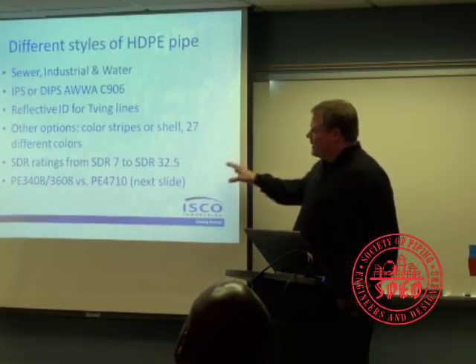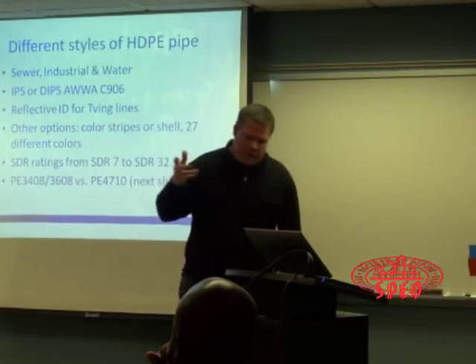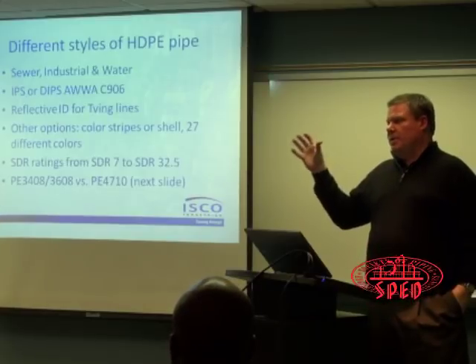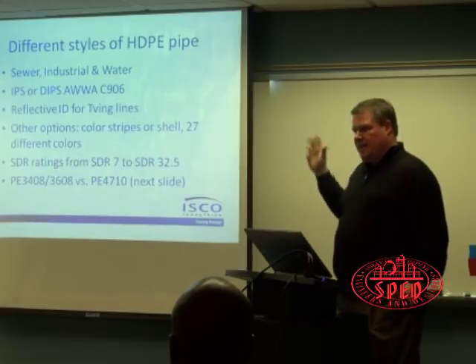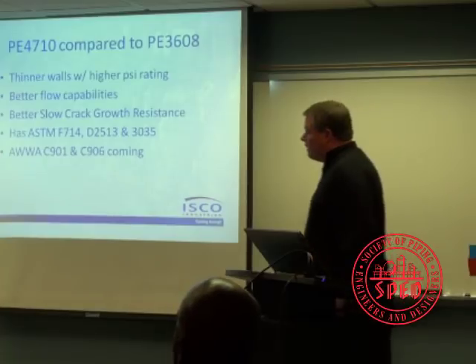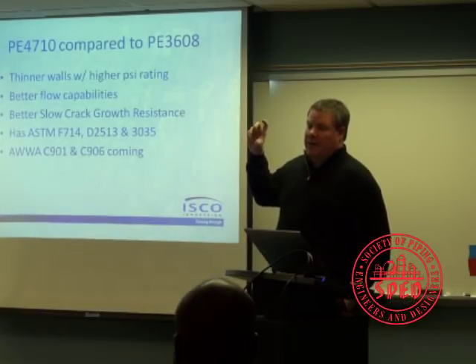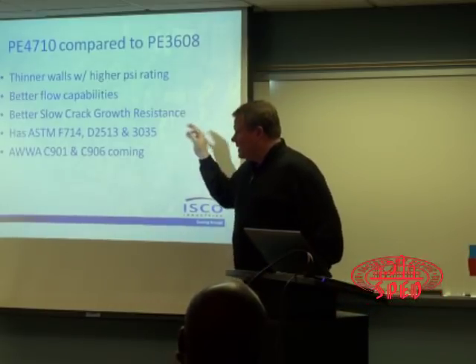The final part of the different styles here. When I came into the business, we were doing 3408. We kind of shifted over to 3608 resin. And now what you're going to see, and we have in our catalog, is 4710 resin, which is basically a PE100 over in Europe. You take the PE100 resin, you drop it into our ASTM standards, it becomes a 4710 is what it's called. And what is this 4710 that we're talking about? It's thinner walls at higher pressure ratings, better flow capabilities, because you have a bigger ID, better slow crack growth resistance.